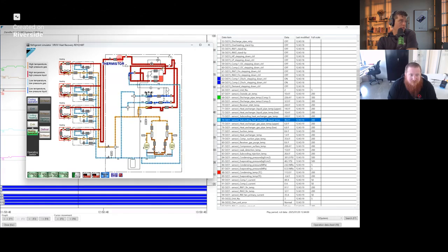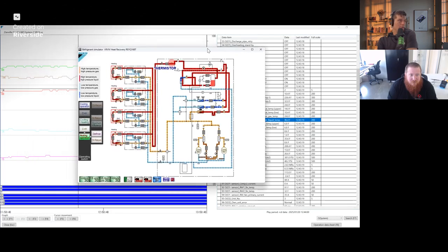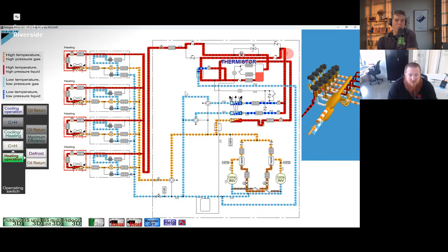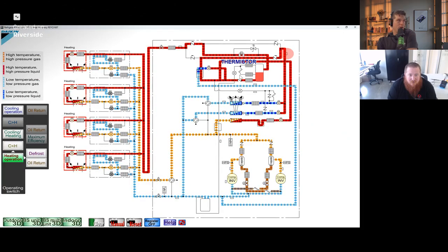And then we're coming over to the actual liquid receiver here, because this is heating mode, so we're going backwards. We don't want to check at the liquid receiver, because we could easily pick up the wrong temperature, right? Because this right here is your liquid receiver temp. So Donald accurately pointed out, in heating mode, we're flip-flopping where we check subcooling. Very important to understand.